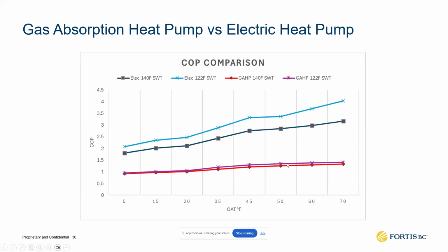And I couldn't find an apples to apples comparison, but I wanted to point out two things to you, and this will be good enough for that matter. Number one is that you see here the electric heat pumps will decrease the COP and also the capacity sharply with outdoor air temperature. So here on the X axis, we have outdoor air temperature. So this will be decreasing with the outdoor air temperature for electric heat pumps, whereas for the gas absorption heat pump, you almost have a flat line. Your gas absorption heat pump does not get much affected by outdoor temperature.